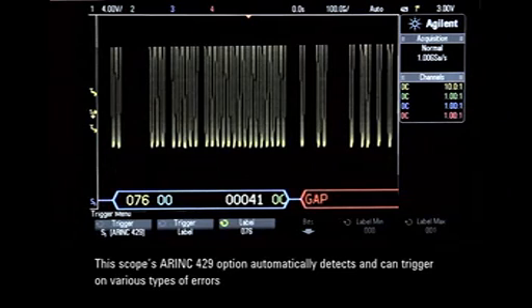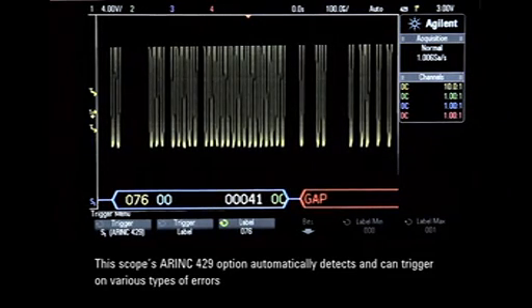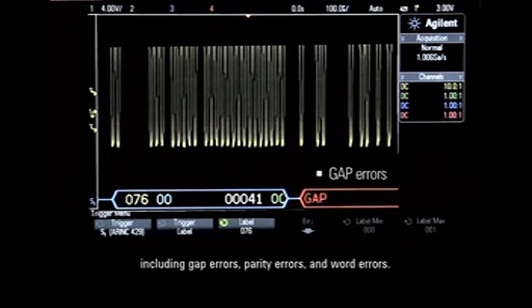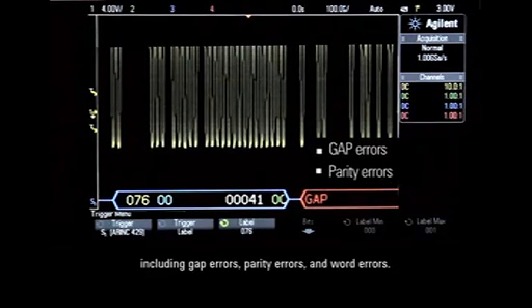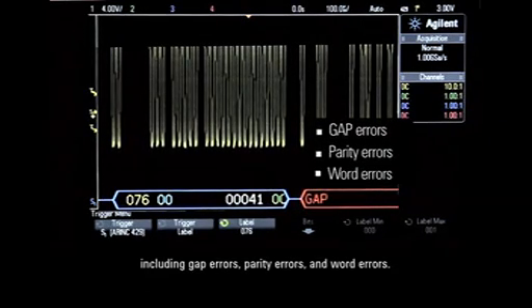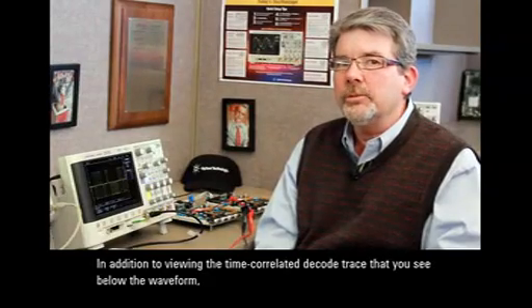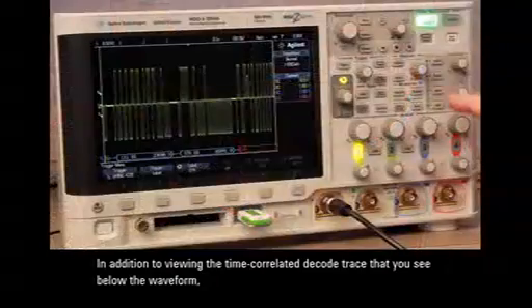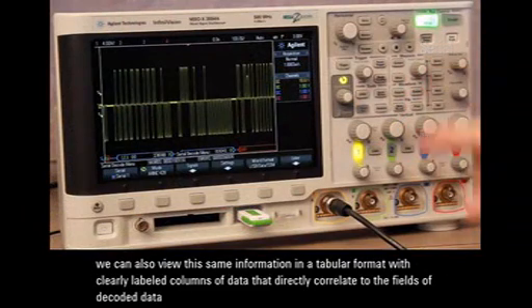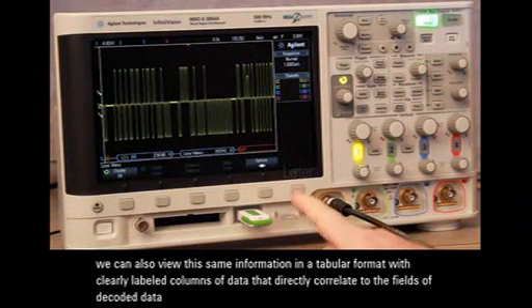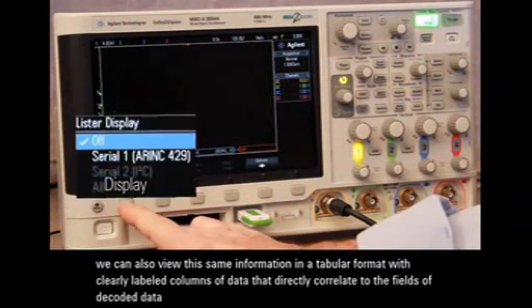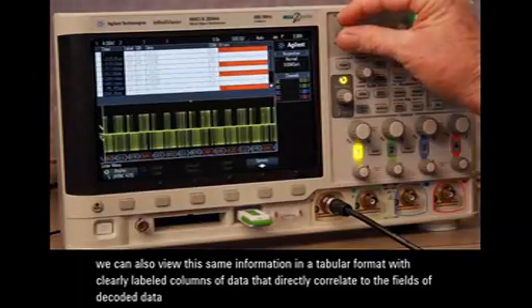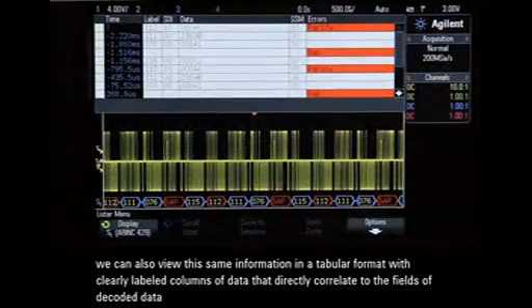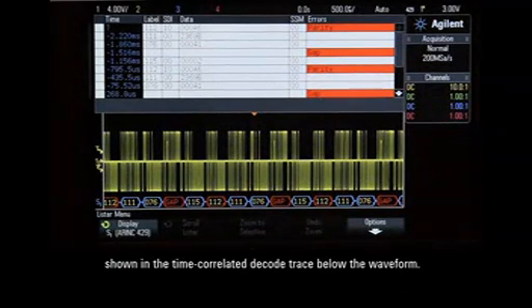This scope's ARINC 429 option automatically detects and can trigger on various types of errors, including gap errors, parity errors, and word errors. In addition to viewing the time-correlated decode trace that you see below the waveform, we can also view the same information in a tabular format with clearly labeled columns of data that directly correlate to the fields of decoded data shown in the time-correlated decode trace below the waveform.